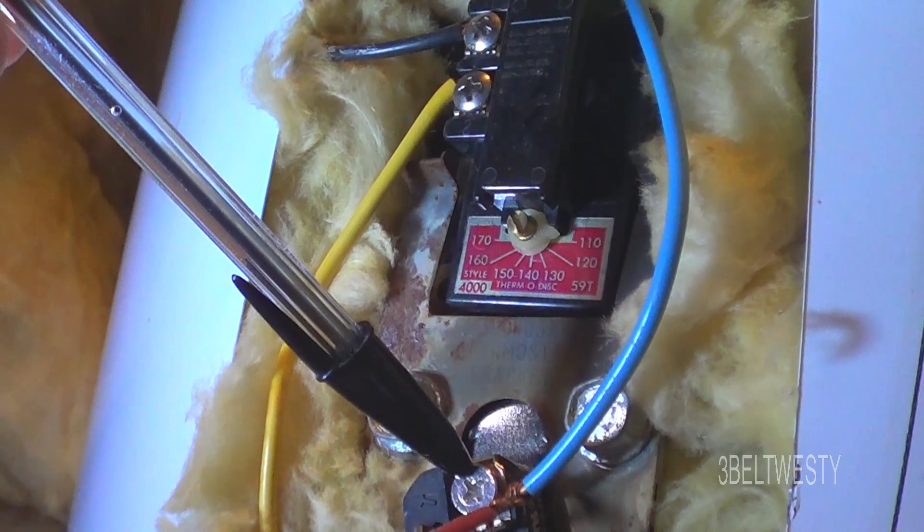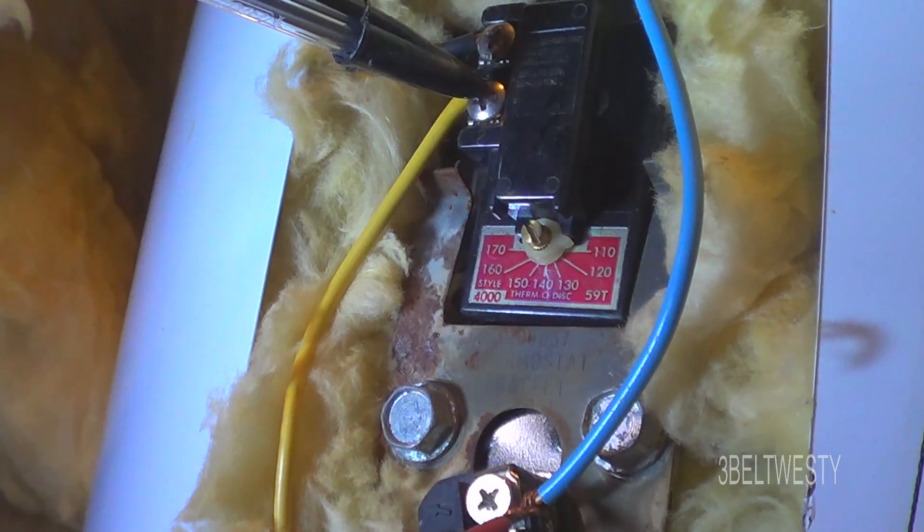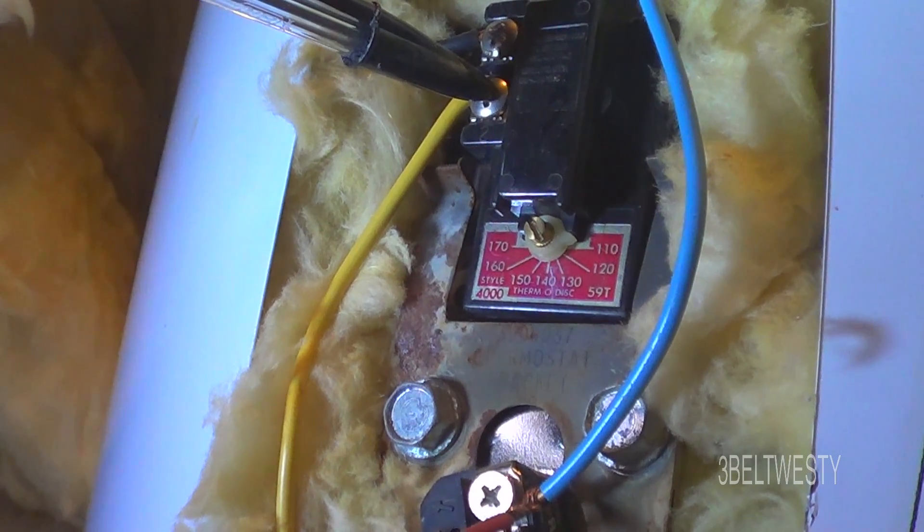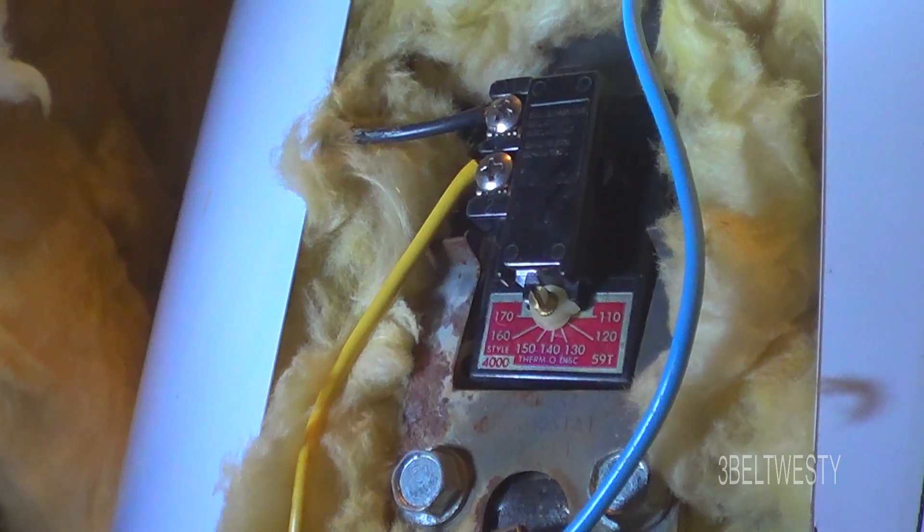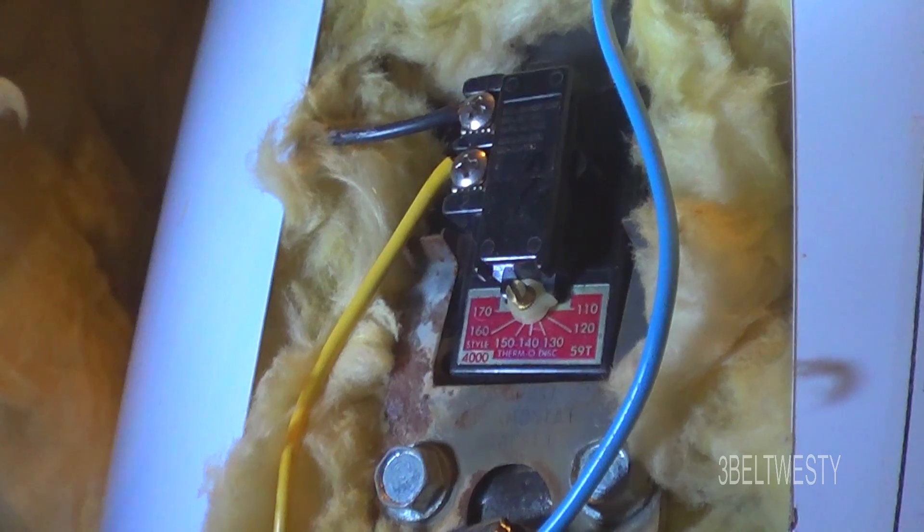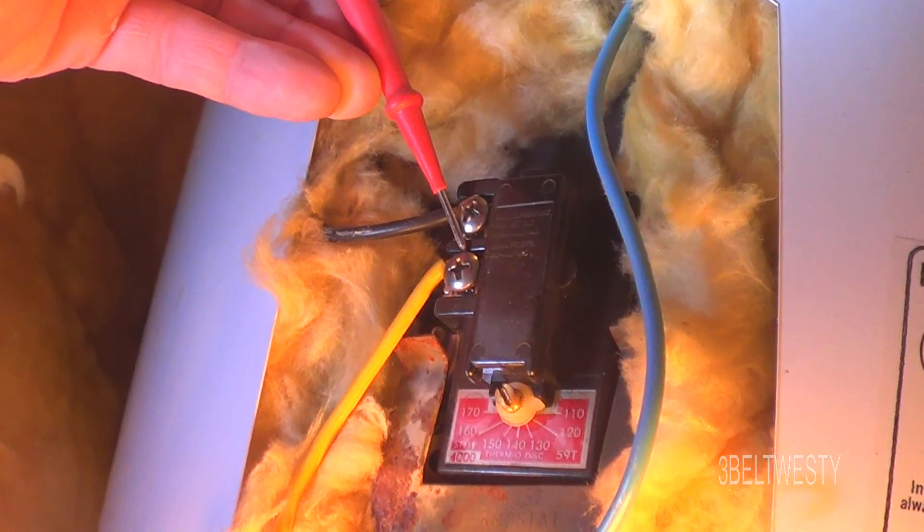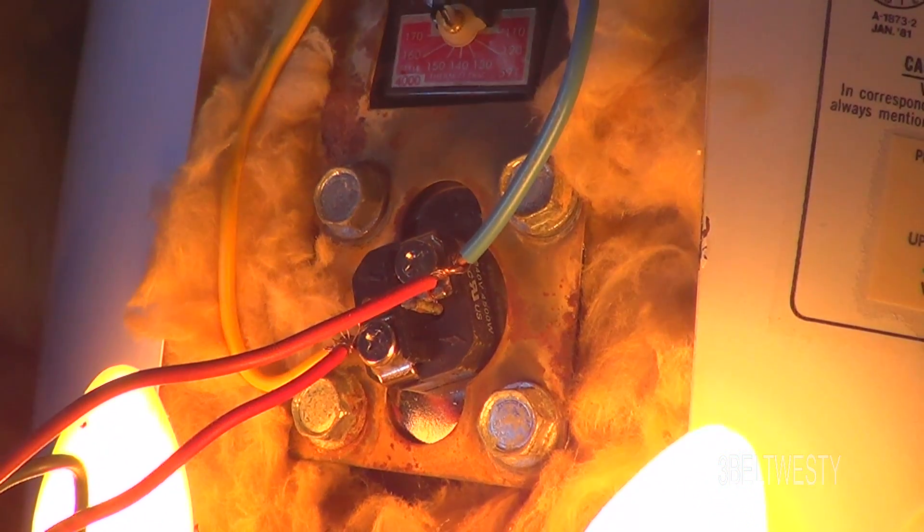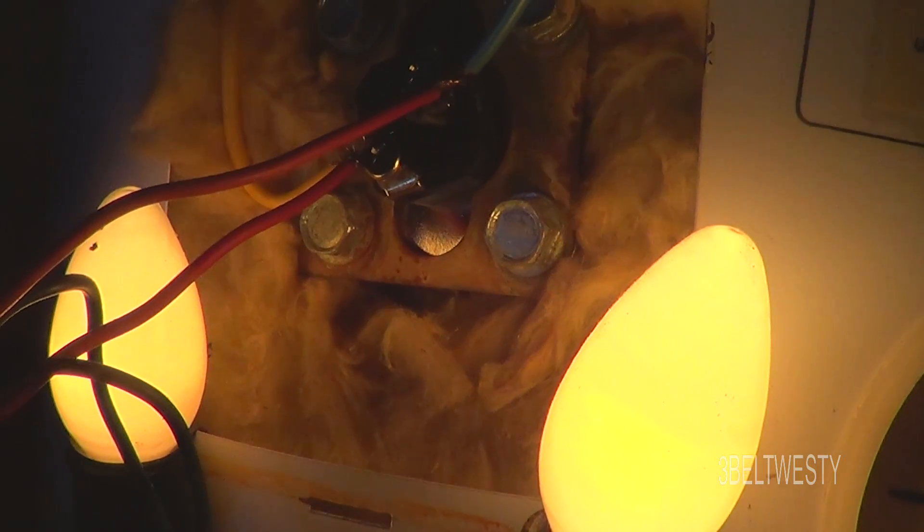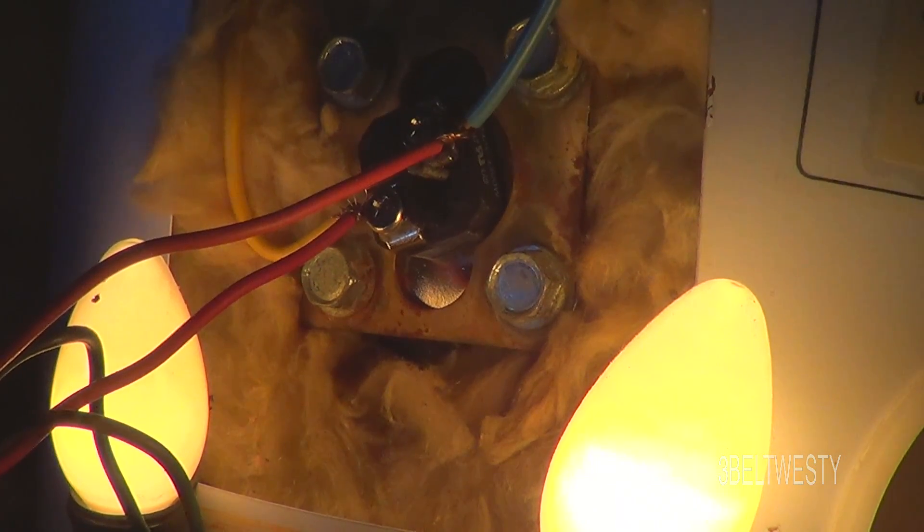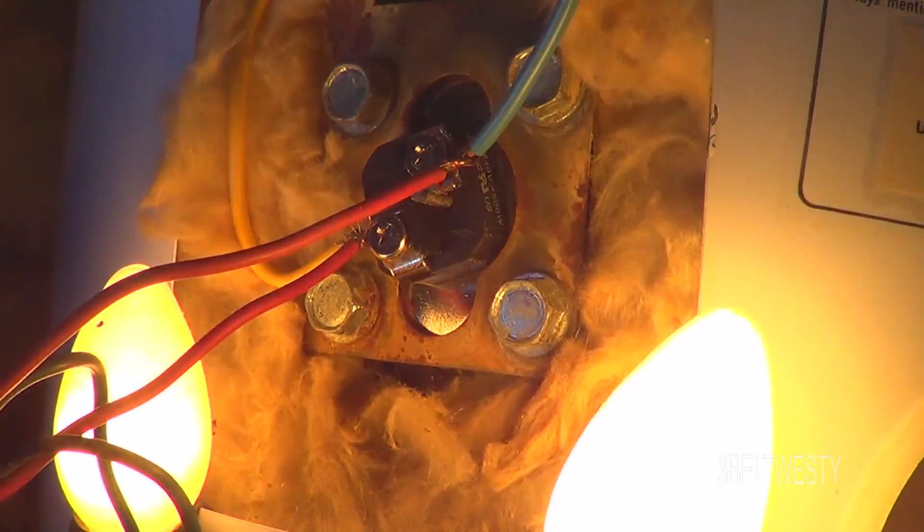This is a lower thermostat and this is hot. This is the switched. If I take that and take a jumper here, I've got power to the thermostat. I've got some Christmas tree bulbs in series. Here's my poor man's 240 volt pilot light.